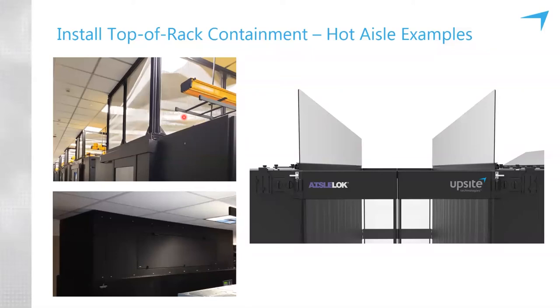So hot aisle containment can be rigid or flexible. If you don't have a ceiling return plenum but do have a high ceiling, hot aisle containment is still an option. In that scenario, you raise the top of the hot aisle containment up from the racks to whatever height the jurisdiction requires — typically 18 inches from a sprinkler head. You would similarly raise the air conditioning unit's intake up, without coupling it to a drop ceiling.